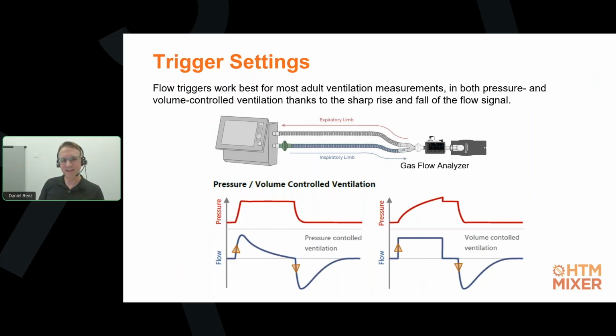And in most ventilator testing applications, you will have a setup that looks a little bit like this one here. So you have your ventilator, you have a dual limb circuit with an inspiratory and expiratory limb, you have your Y piece, and then you connect your gas flow analyzer after the Y piece and a test lung after your gas flow analyzer. So in such an application, you will always have a positive flow through the gas flow analyzer in inspiratory phase, and then all the gas goes back through your gas flow analyzer in a negative flow, or the opposite direction, back to the ventilator.